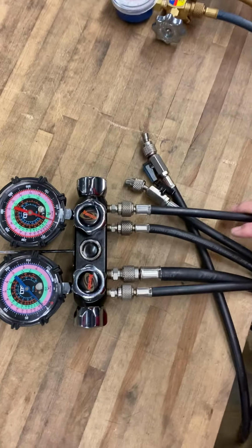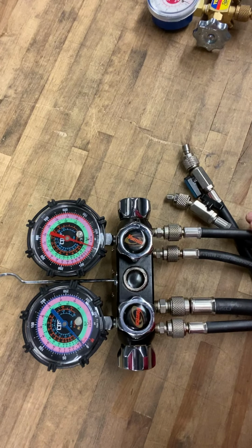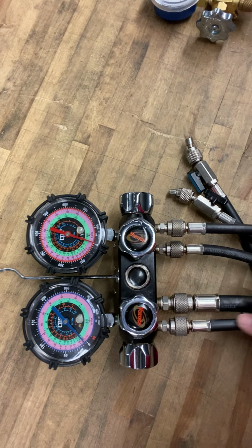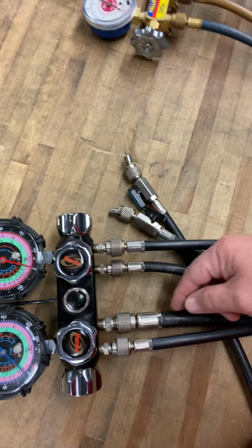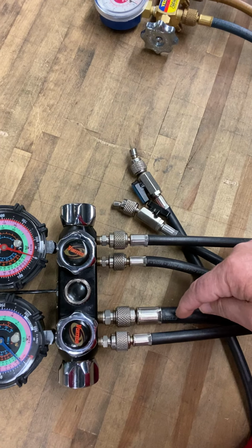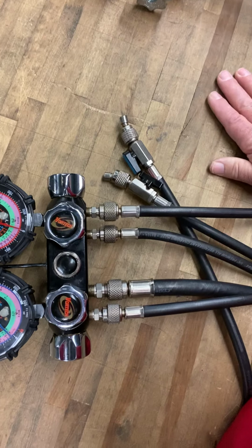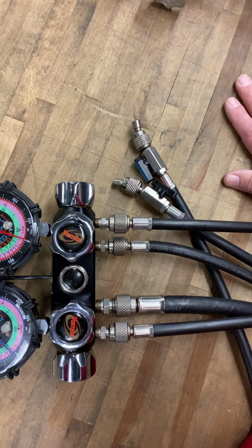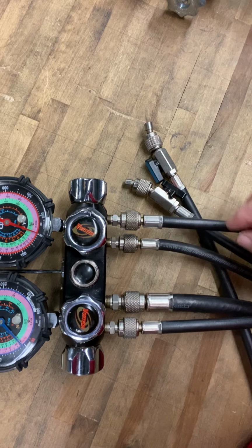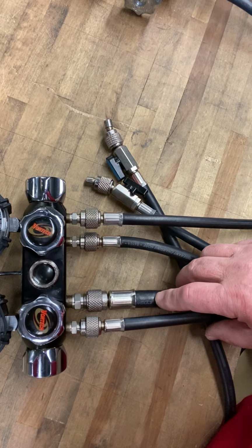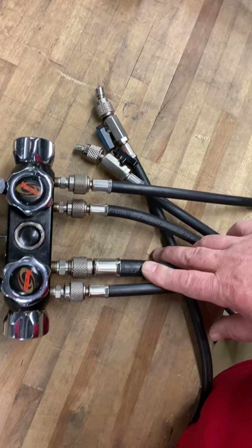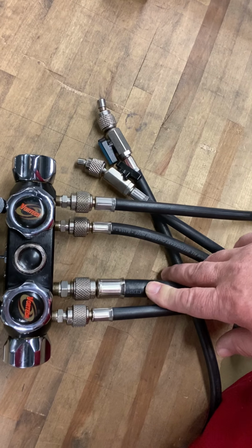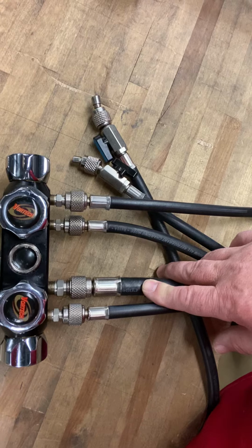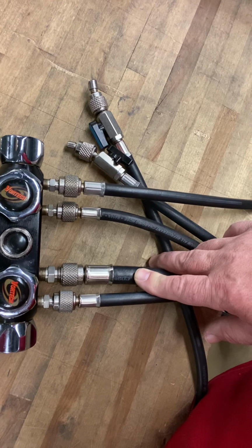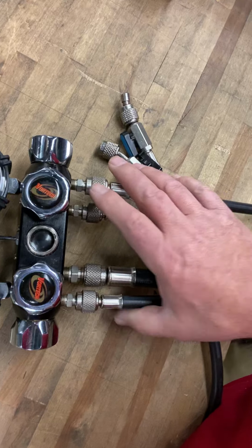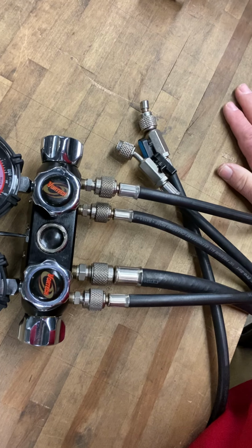So this one right here is a 4-hose set, 1, 2, 3, 4 hoses. You can see on there this hose right here is a little bit oversized. The reason you have 4 hoses on here is this is really an installation manifold set. You have more connection points, and this oversized hose which aids in the speed of evacuation. So probably not something you want to lug around as a service tech or demand service tech where you're troubleshooting. If you're getting in and out of the truck 6, 8, 10 times a day, you don't want to grab these, kind of bulky and heavy.